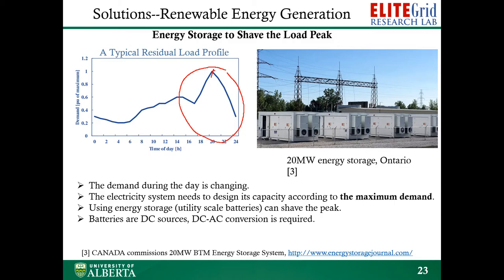But if we have energy storage components, we can shave the peak, because power does not need to be transferred from the grid. It can be fulfilled by the local energy storage, so the batteries can inject power to the grid and it's consumed by the customer. So the transformer or the transmission line do not need to be designed based on the peak load.